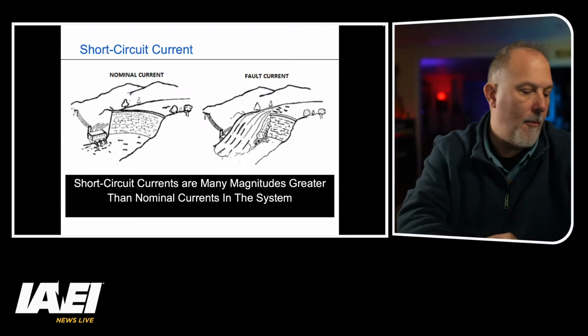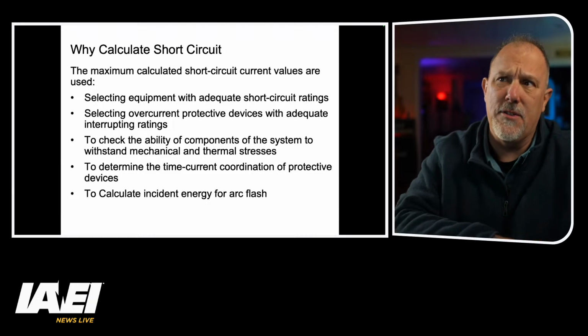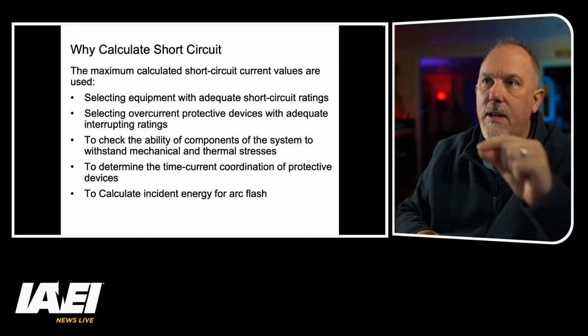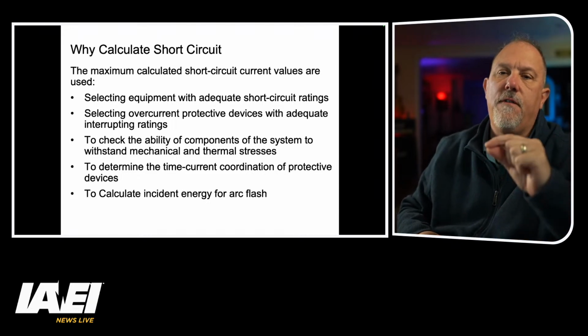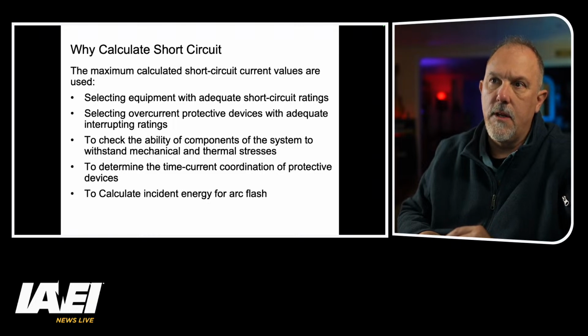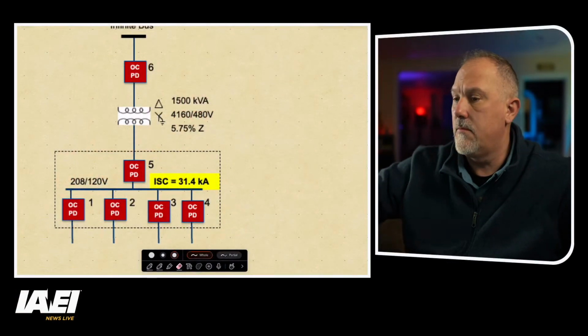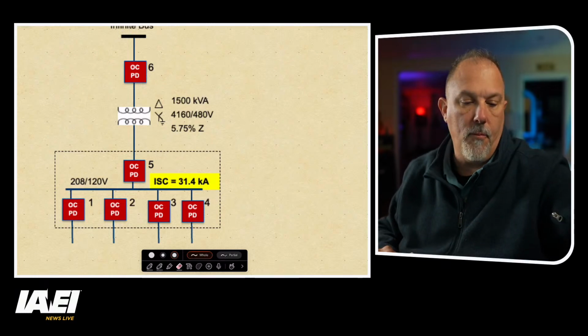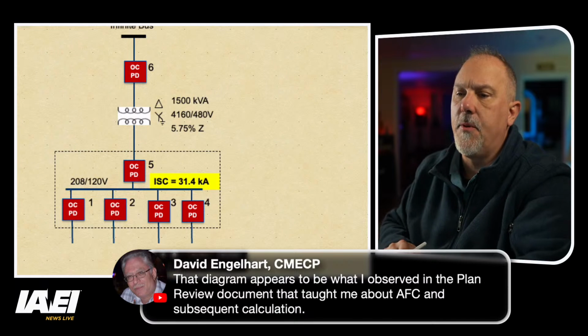So, I got people texting me and all that good stuff. So why do we calculate fault currents? We calculate fault currents for various reasons. I will calculate a maximum available fault current to do equipment evaluations. We have to make sure that in a power distribution system, say a power distribution system like this, that diagram appears to be what I observed in the plan review document that taught me about available fault current.